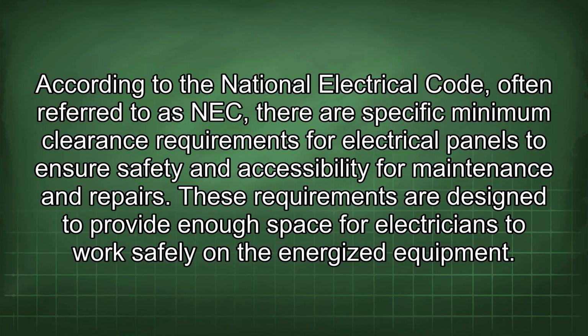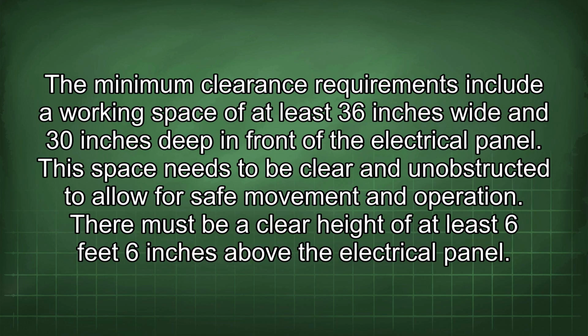According to the National Electrical Code, often referred to as NEC, there are specific minimum clearance requirements for electrical panels to ensure safety and accessibility for maintenance and repairs. These requirements are designed to provide enough space for electricians to work safely on the energized equipment. The minimum clearance requirements include a working space of at least 36 inches wide and 30 inches deep in front of the electrical panel. This space needs to be clear and unobstructed to allow for safe movement and operation.